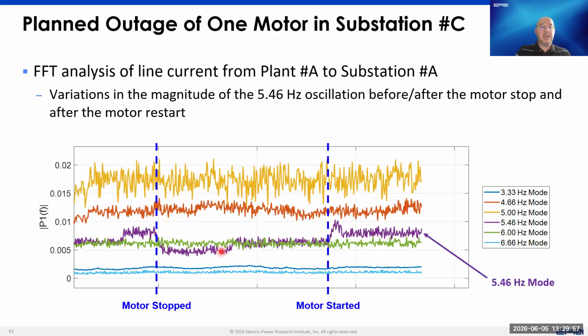So we suspect here that the load customer further increased the loading of the other motors within the substation to basically bring the production level back to the same level as it was before the plant outage. So you see that after that small increase, the level is similar to what we had initially. And then we get to the point where the motor was restarted, and you see here the increase as expected with the motor restart.